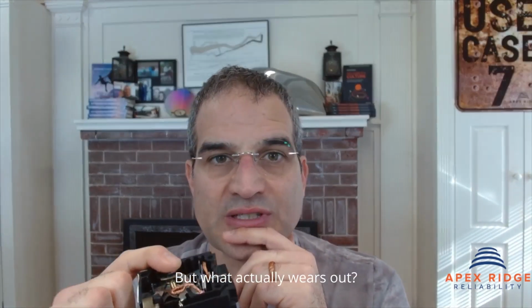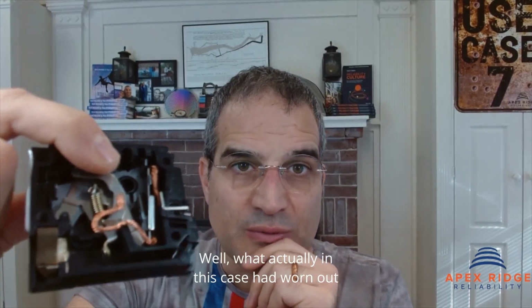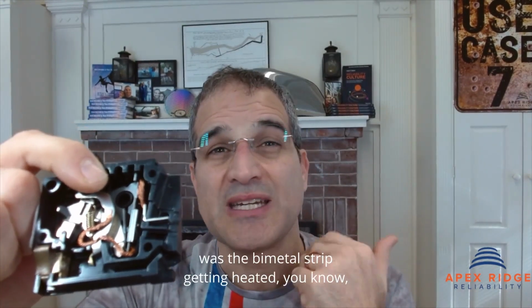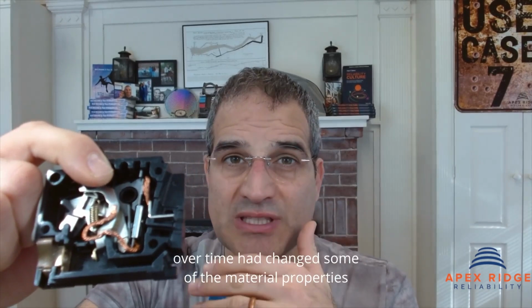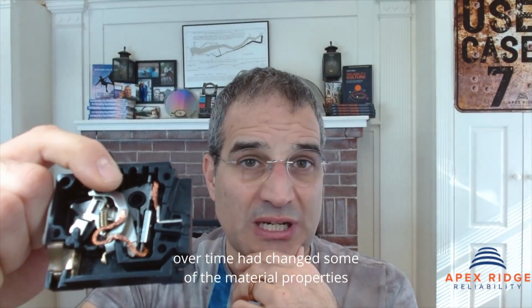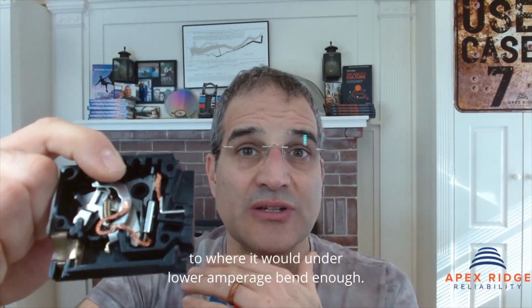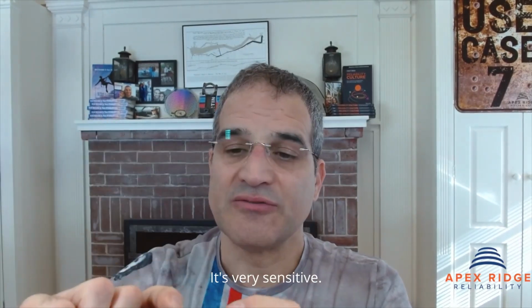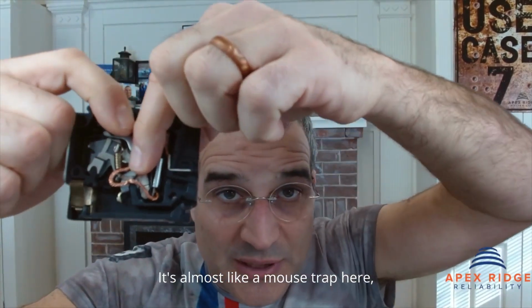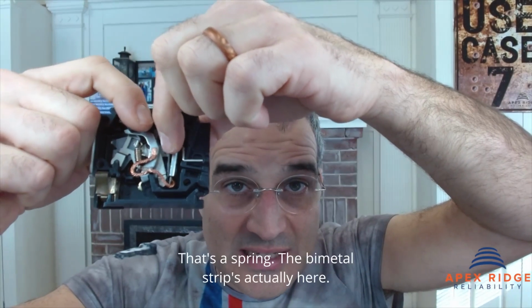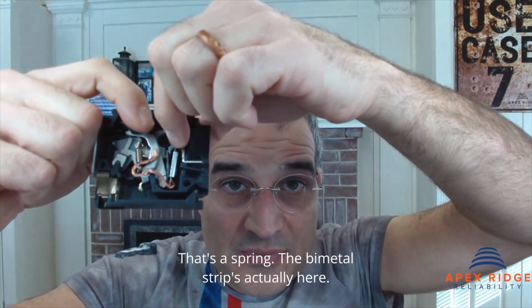But what actually wears out? Well, in this case what had worn out was the bimetal strip - getting heated over time had changed some of the material properties to where it would bend enough under lower amperage. It's very sensitive, almost like a mouse trap. That's a spring, the bimetal strip's actually here - very little motion, it'll flip.